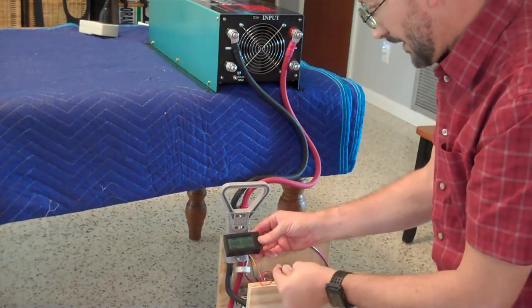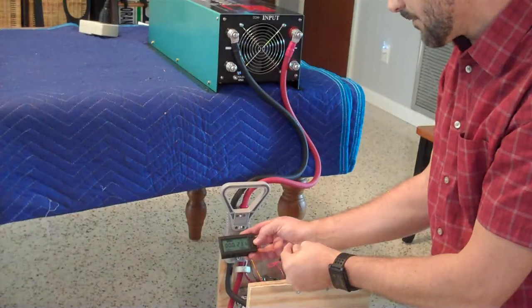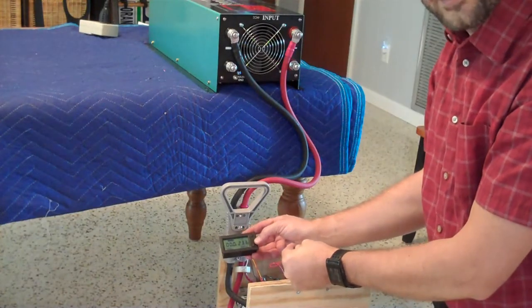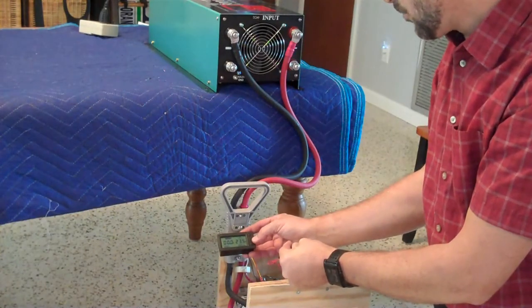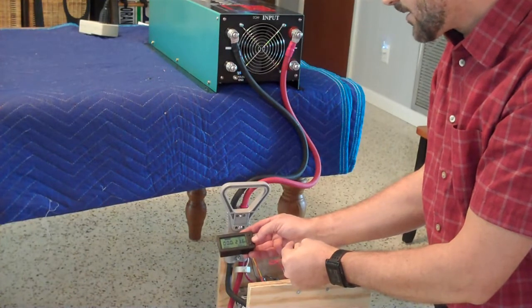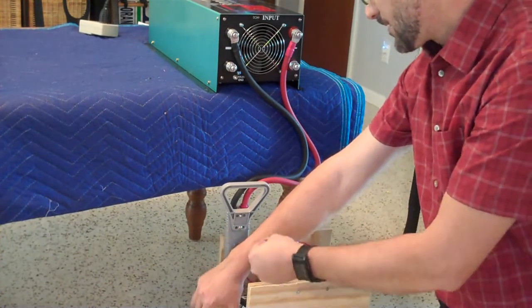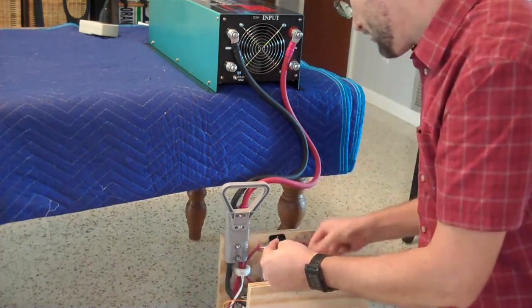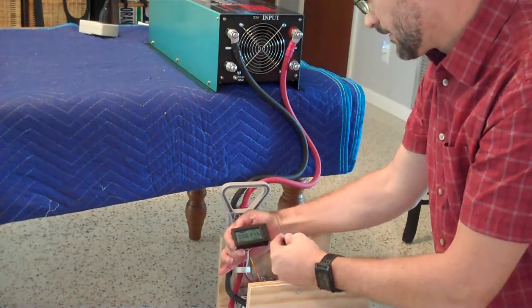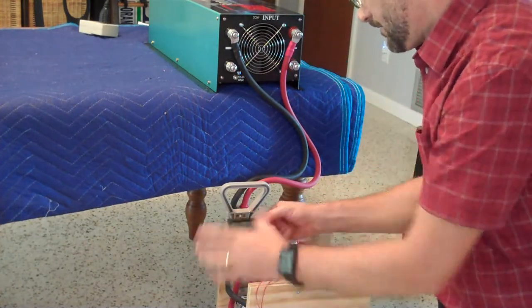So, push the button, it charges up. We're at 13 volts, 14 volts, 16 volts, 18 volts. It's equalizing the capacitor slowly, and we're up to 22.4, 22.9, 23 volts. So now the capacitors in the inverter are basically equalized with the battery, and it's safe to turn on the main disconnect.